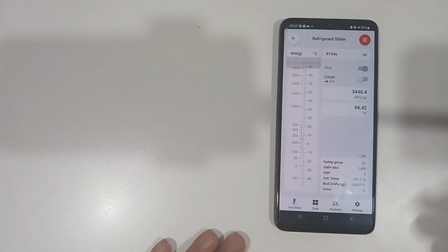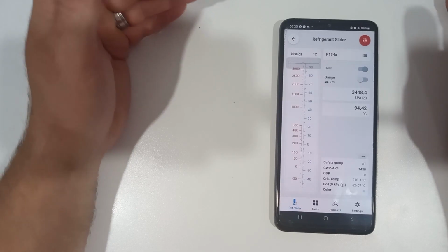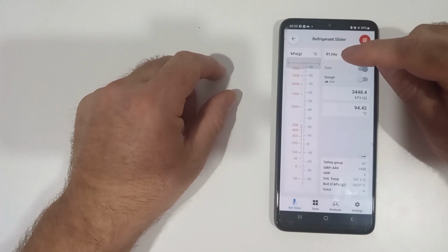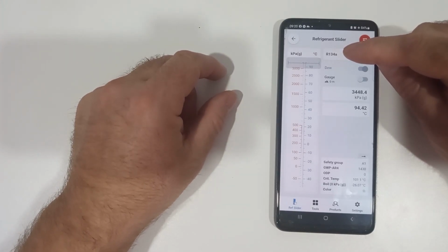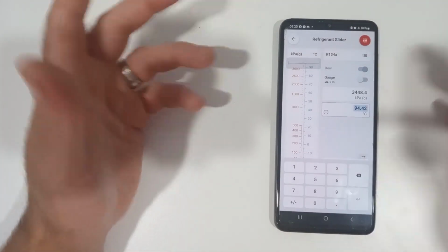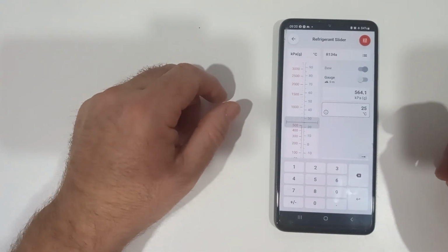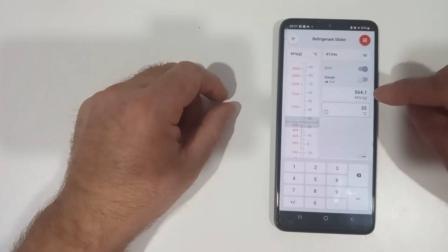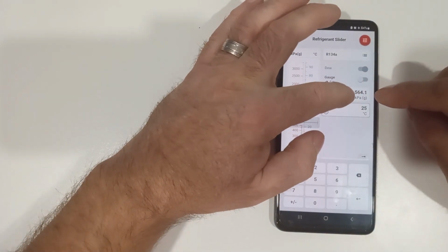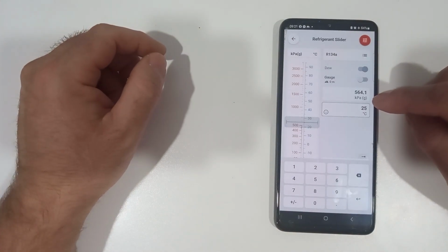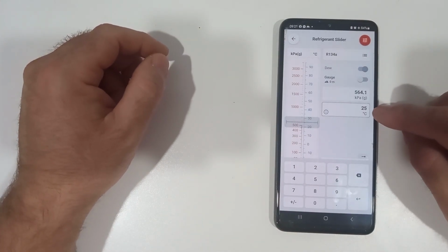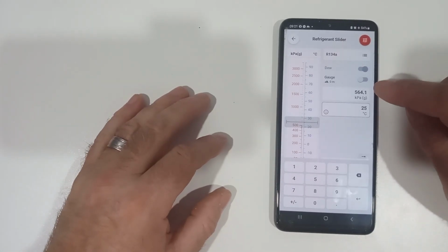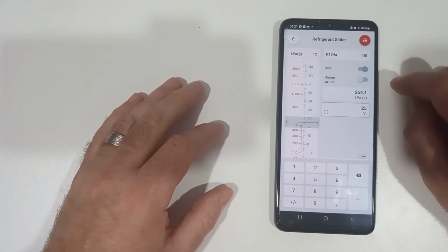What we would normally do is, let's say we want to work out the pressure of the refrigerant inside a cylinder. If we know it's 134A, and we get our fixed temperature or ambient temperature of 25 degrees C, we can work out if it's pure 134A by putting our gauges on. If it's 564 kPa gauge, then at 25 degrees C, pure R134A will be 564 kPa.